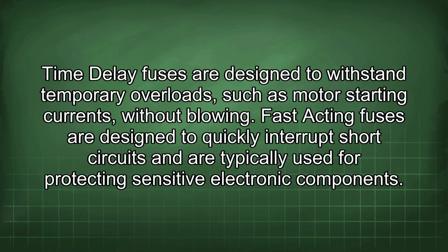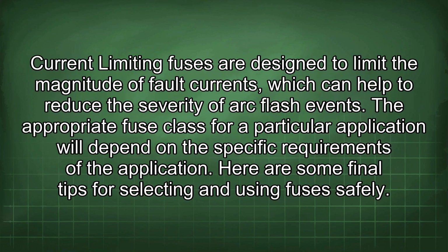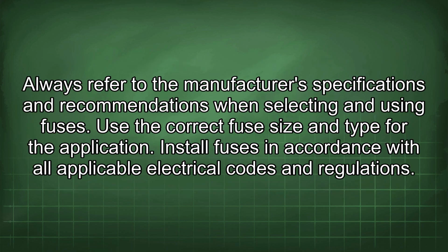Fast-acting fuses are designed to quickly interrupt short circuits and are typically used for protecting sensitive electronic components. Current-limiting fuses are designed to limit the magnitude of fault currents, which can help to reduce the severity of arc flash events. The appropriate fuse class for a particular application will depend on the specific requirements of the application. Here are some final tips for selecting and using fuses safely. Always refer to the manufacturer's specifications and recommendations when selecting and using fuses.